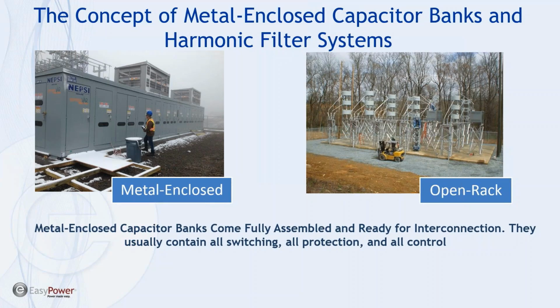On the right is an open rack solution. It's an alternate form of the metal enclosed solution on the left. This system typically comes piecemeal. It requires assembly in the field. It's often not integrated like the systems sold by NEPSI. And as you can see here, everything is built at a height of at least 3 meters, 9 foot 6 inches, and therefore you need lift trucks and things like that. They utilize air core reactors, whereas in the metal enclosed system we use iron core reactors. So that's primarily the main significant difference between the metal enclosed system and the open rack system.